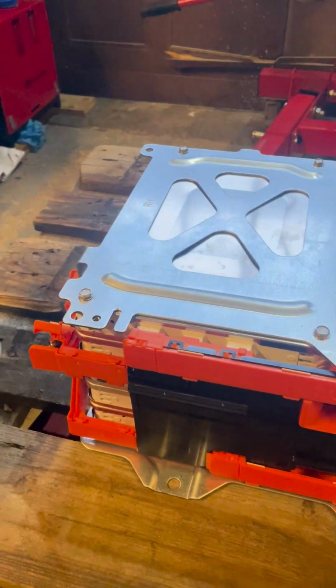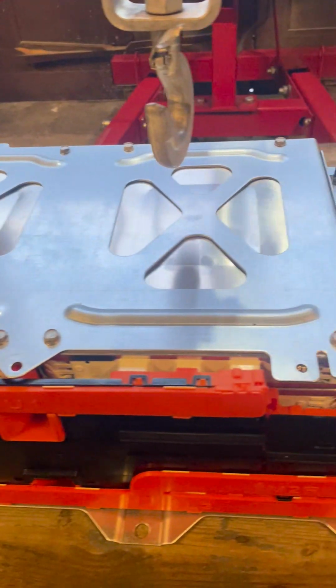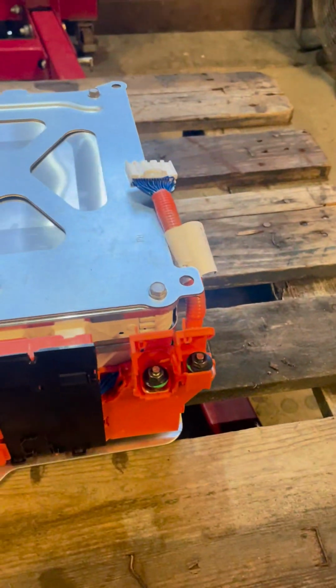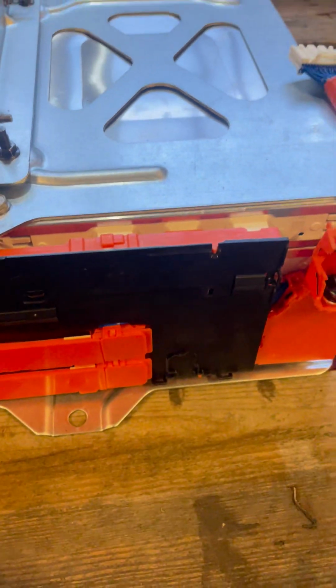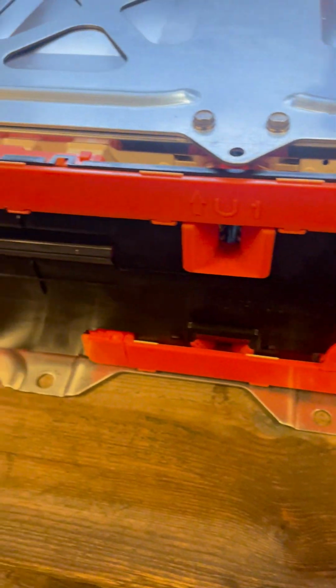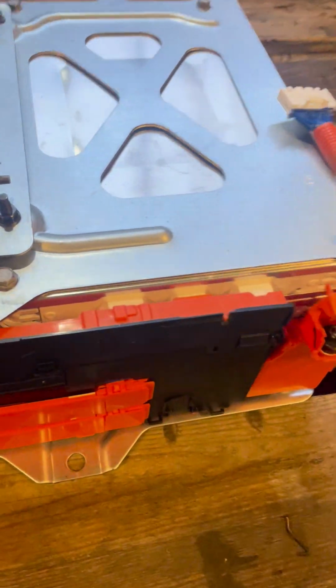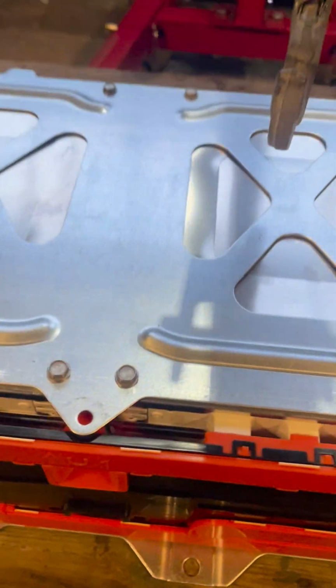So because these are clamped into their assembly vertically rather than horizontally like the back section, all we've got to do on these ones is get the covers off the bus bars, get the bus bars all undone with their bolts and their screws, pull off the plastic like we did on the last one, and then we just undo the bolts that go down through the retaining plates, and we're away.